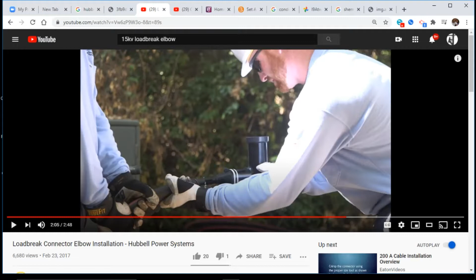The final seating of the elbow should align the elbow and threaded portion of the lug. Wipe off. So he's going to do exactly what you need to do here. Remember, the eye of the lug that was on top was threaded. You need to get that in line with the elbow right here so you're able to thread the tip in. He's looking down to see where his threads are.